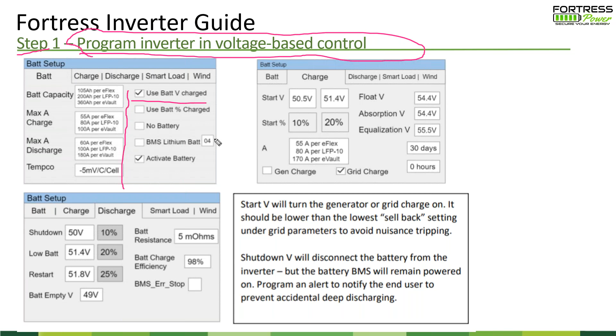The advantage of using voltage-based controls as the starting point is that you can then program all the functions as a function of voltage rather than percentage. This gets you that voltage-based fallback programming in place in case there's ever a drop in communication between the battery and the inverter. Then you can go back and program the percentage-based controls.